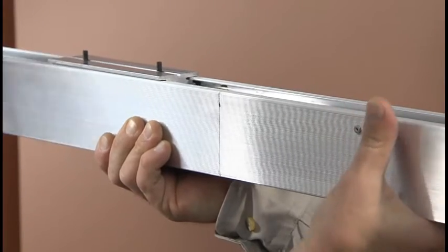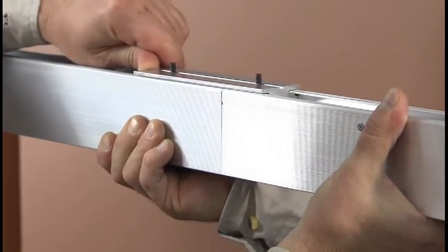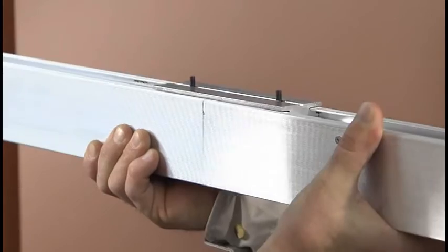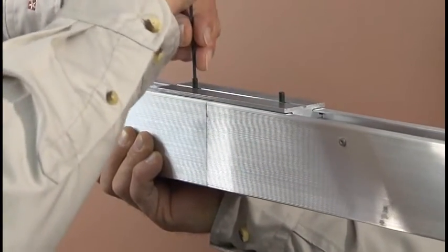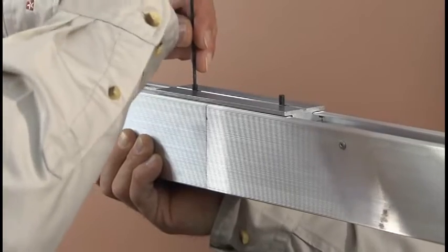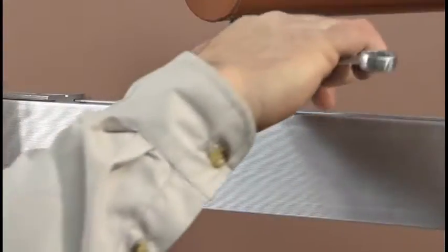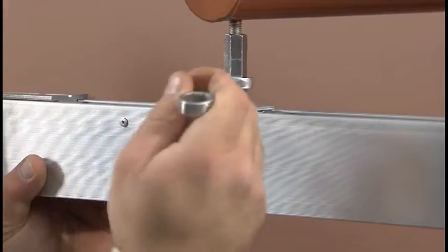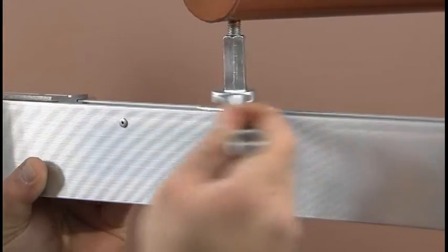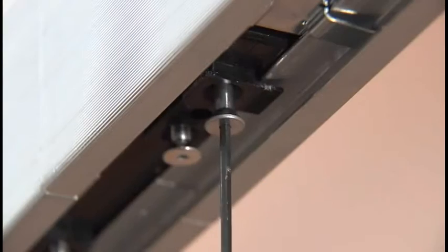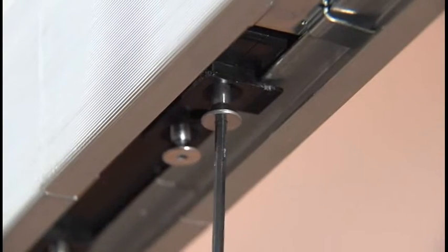With a 3/32nd Allen wrench, center the housing coupler over the joint and tighten the set screws or bolts. Tighten the hangers on the second section of the busway. Repeat these steps until the busway is complete. Then, tighten the four set screws on the bottom of the bus connector.